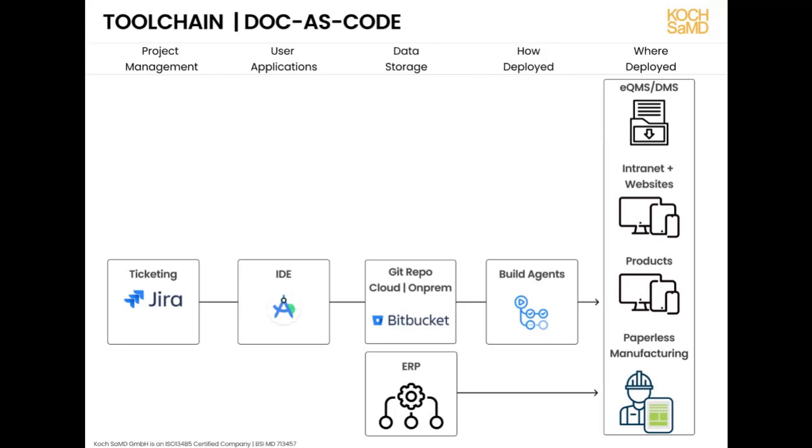So often, if you look at a technical file, it can be deployed to maybe 100 regulatory dossiers if you have a global footprint, for example. So you've got the same bit of content, an intended use statement, which goes in the FDA, goes in Canada Health, goes in the EU, the UK, Australia, wherever it is. So there's a lot of duplication of content. And the nice thing about this approach is you can have source control on the content, and through the build agents, you can actually automate the building of your technical files. You can automate deployment of text to product websites, to in-product content.